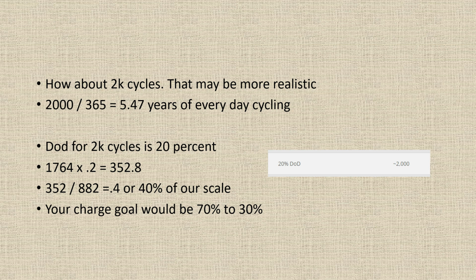So if you want 2,000 cycles, that's 5.47 years if you cycle it every single day. Your depth of discharge at 2,000 cycles is about 20%. So you take 20% of your 1764, and that's 352.8. 352.8 divided by 882 watts for your scale is 40% of our scale.